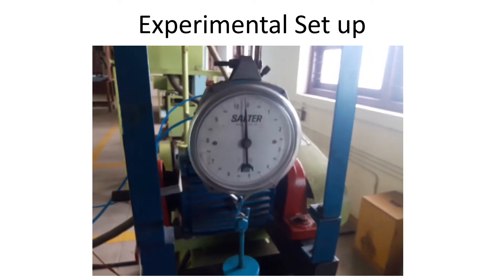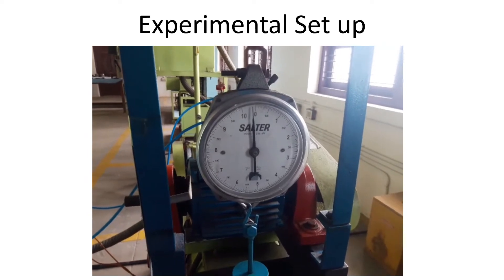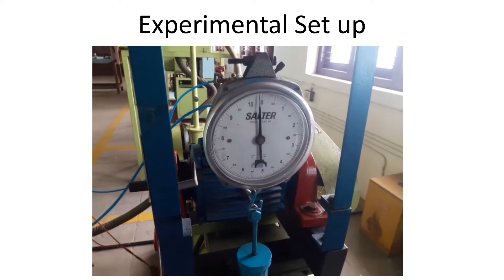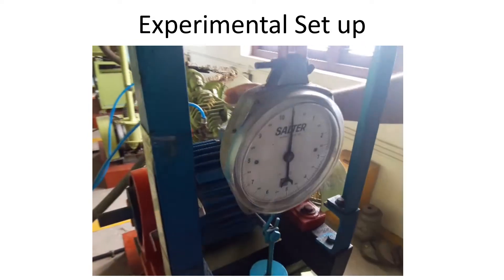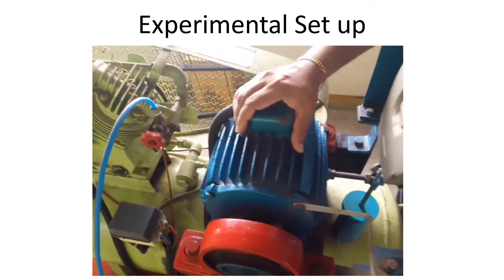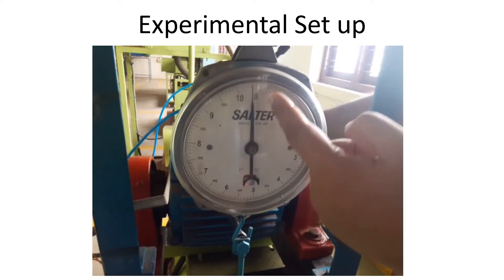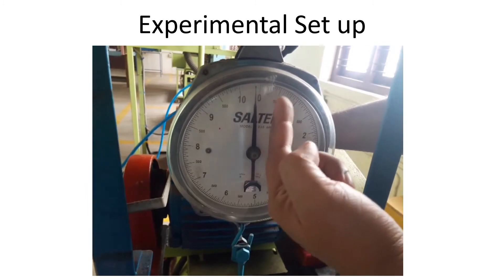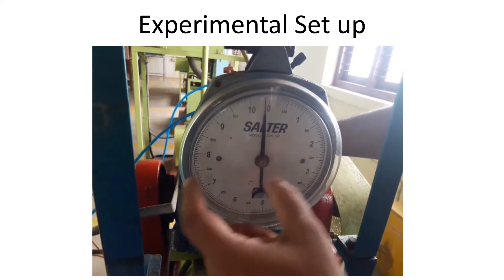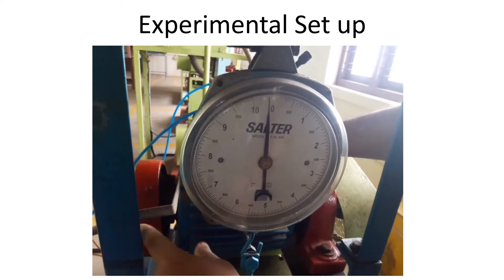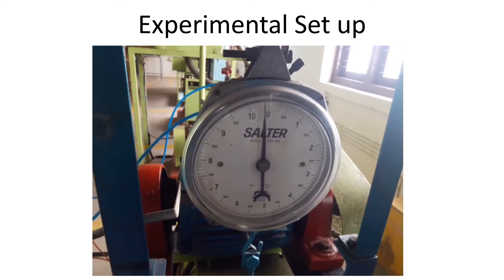When the delivery valve is slightly closed, the pressure will increase. Automatically, more power is required for the compressor to work — and we get that from the output power of the motor. The output power of the motor can be determined from the spring balance. When more power is taken, some force in terms of kilograms is noted, and that is multiplied with the arm length of the motor to get the torque. Once we get the torque, we can very easily find out the power, which is equivalent to the input power of the compressor.